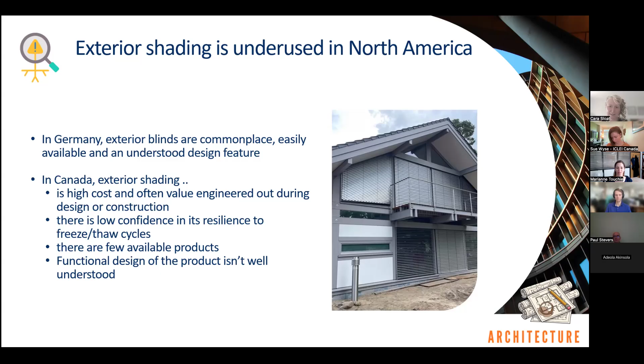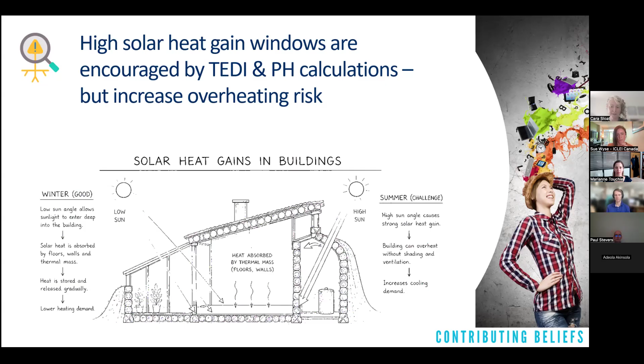In our well-meaning search to create high performance buildings, we've encouraged high solar heat gain windows by creating a new metric called the TEDI, the Thermal Energy Demand Index — how much energy over the course of a year a building needs for heating. We created a maximum on that, which you can drive down by increasing the amount of solar gains in the space. We don't have an equivalent metric for cooling energy demand, so there's no control in this high performance building metric that discourages designers from creating overheating spaces.